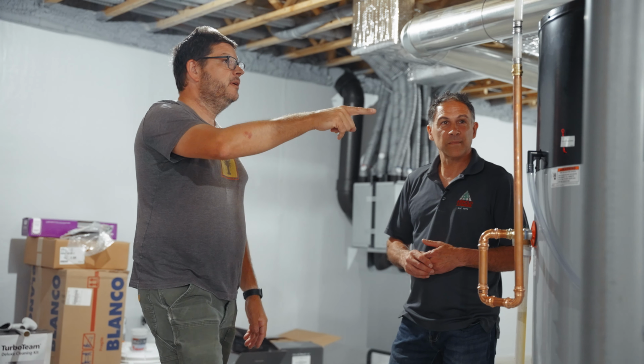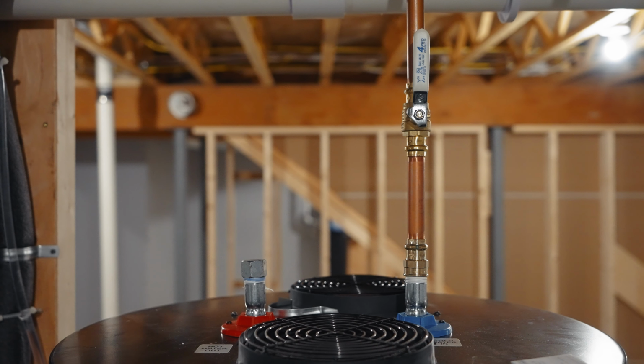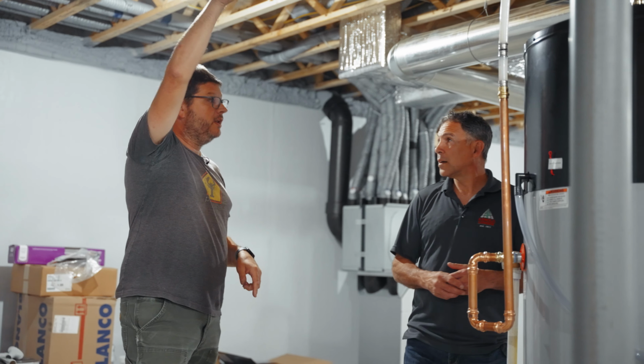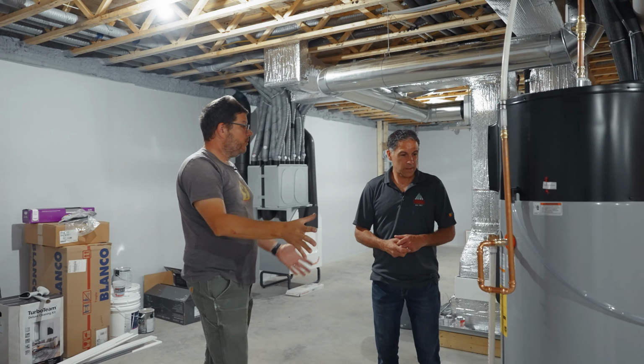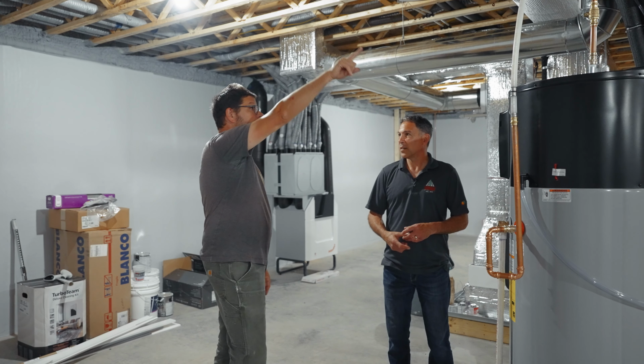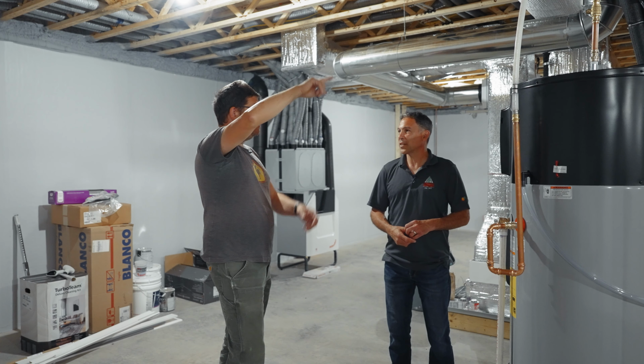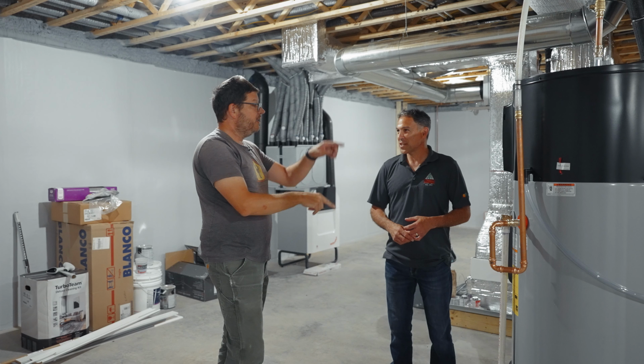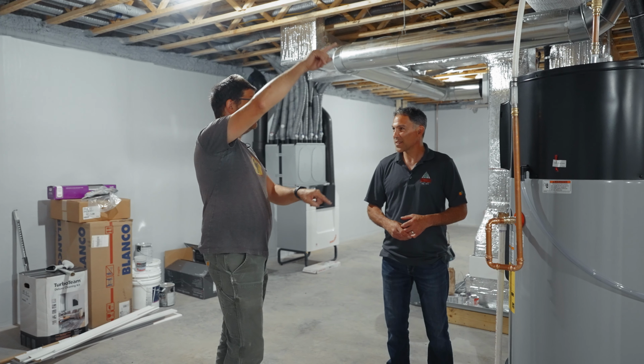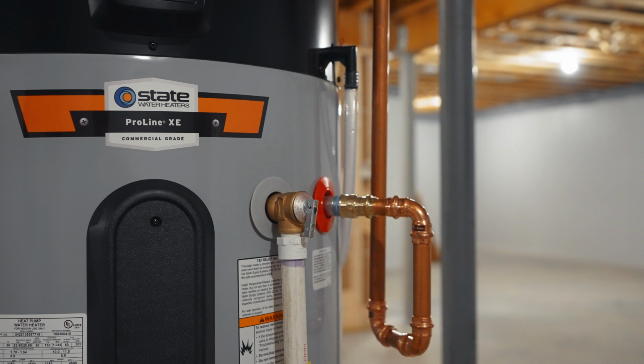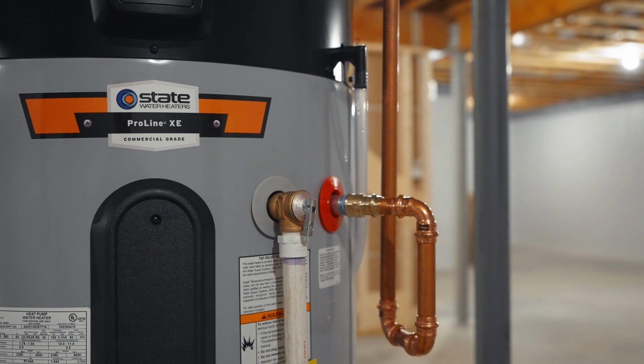If you take a water heater with a hot water tap on top and the pipe going straight up, while you're not calling for water, the water in the pipe starts cooling and sinks down into the tank, pushing hot water up. A loop in the pipe short circuits that, cutting off the opportunity for it to happen. So if this is a summer house and the hot water heater is on for a couple months between visits, you're not losing that heat. Why not just put that little loop on and get the extra efficiency?